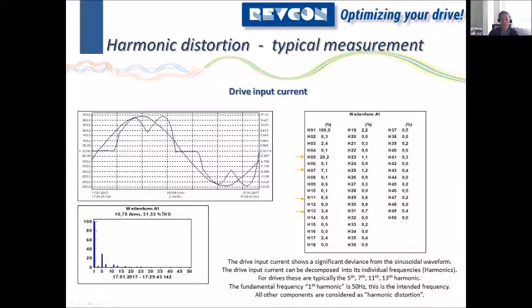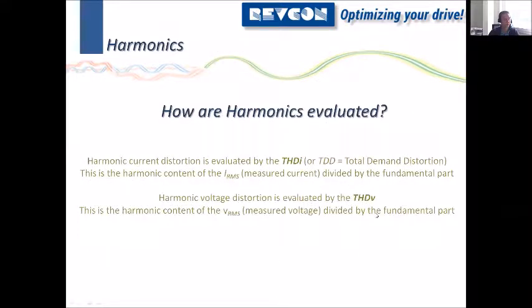Okay, so that's all that I had to tell on this THDI or total demand distortion, TDD, which is a little bit similar, but not exactly. I will tell you later on more. Basically, both of them are two contents of the IRMS, the harmonic part divided by the fundamental part. And this relationship between those two gives you information about the quality of your current. And for the voltage, it's exactly the same, just using the voltage amplitude instead of the current amplitude.